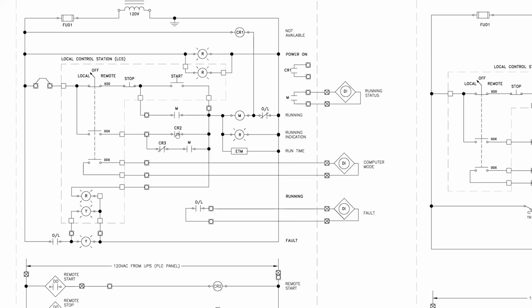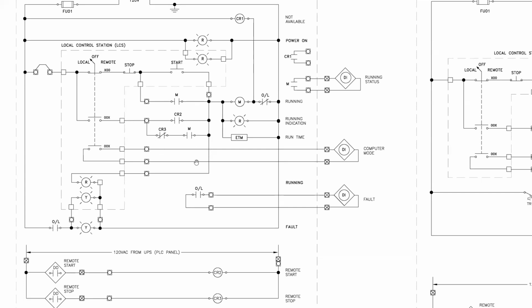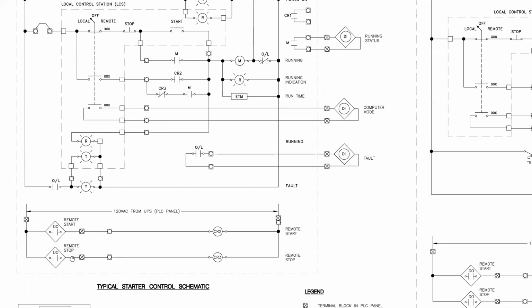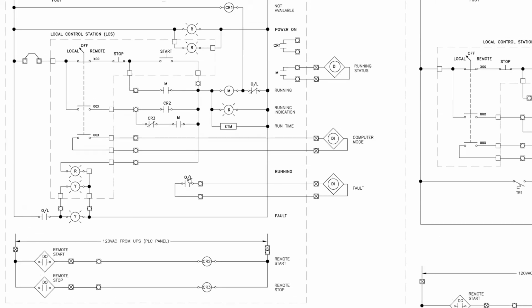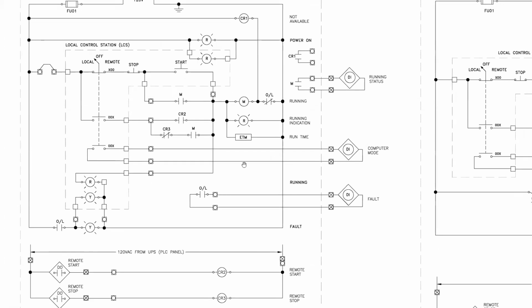In remote, CR2 and CR3 look like they work. CR2 will turn on M, which will seal itself in. And then CR3 will stop the pump. We've got a light for run indication. ETM, elapsed time meter. That's the run time of the pump. Here's an overload contact. Overload contact. Those will physically be attached to the pump starter, and they will trip when there's a fault condition. Motor current overload. Maybe there'll be a temperature sensor, something else wired to it.